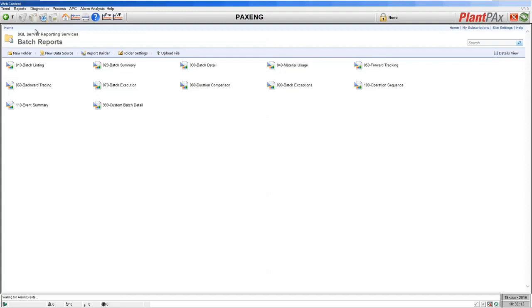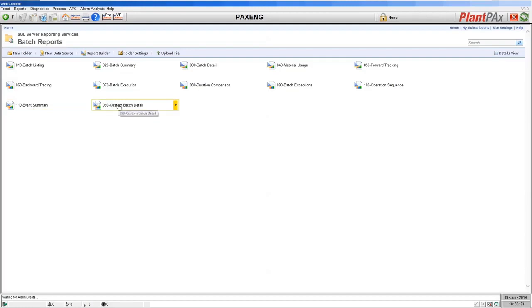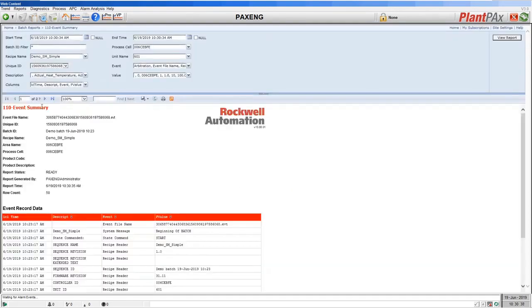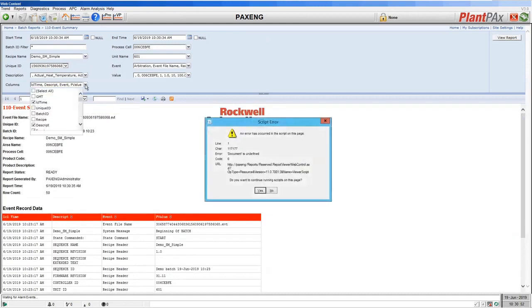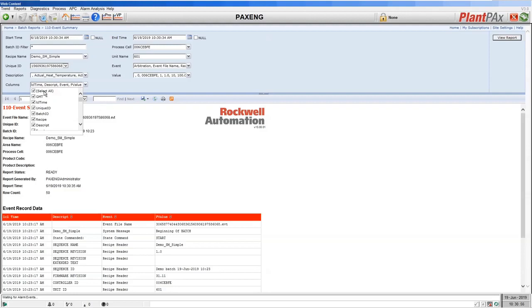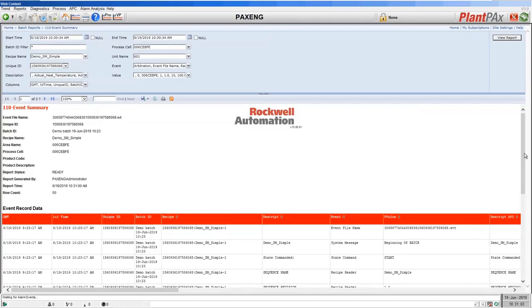Finally, we have three more reports: the operation sequence report, which is only available if you move to FactoryTalk Batch; the event summary report, available for both Sequence Manager and Batch; and a custom batch detail report I've created to show that reports can be customized. The event summary report shows all of the events logged into our SQL database by Sequence Manager as we ran that sequence. You can customize it and decide which values from the database you wish to display. Let's select all values and scroll through the details.